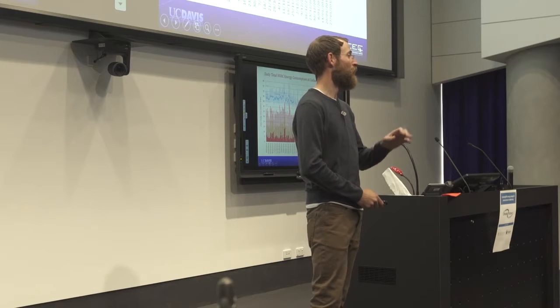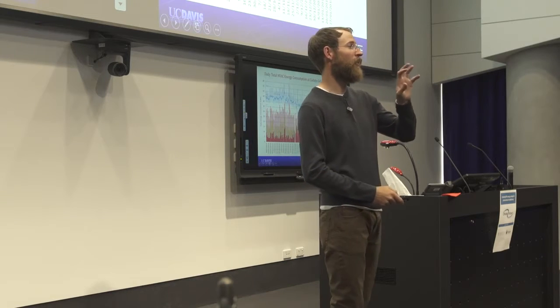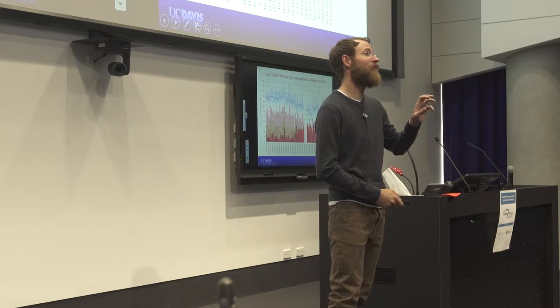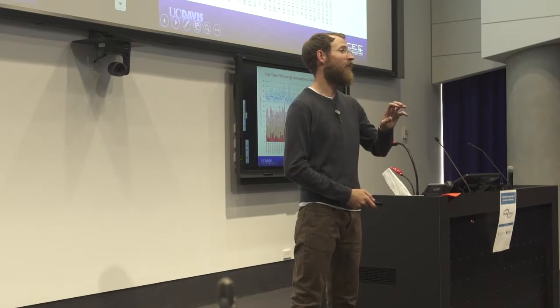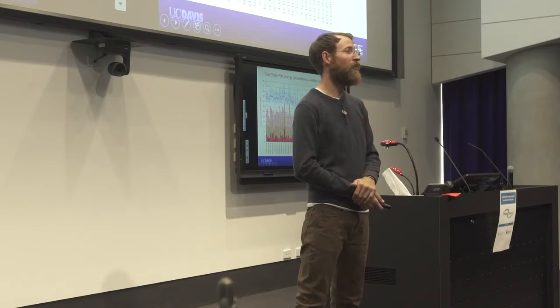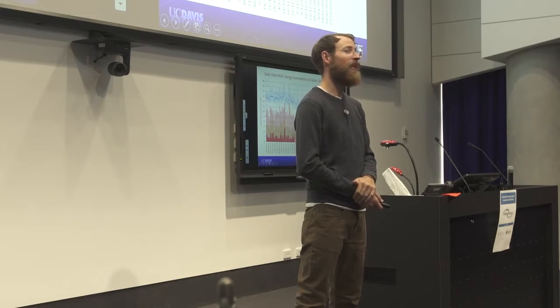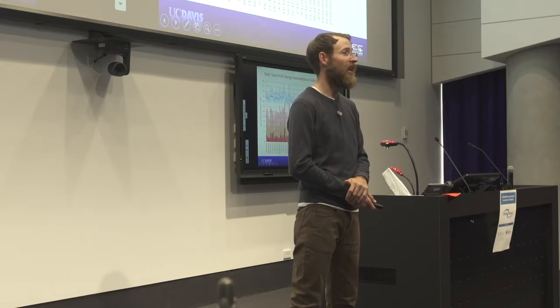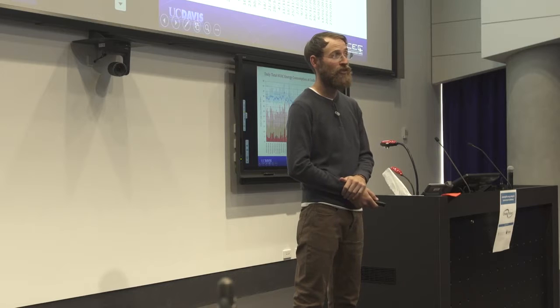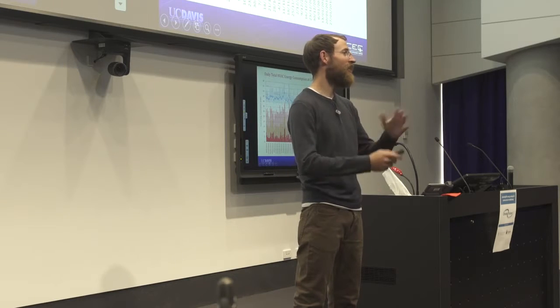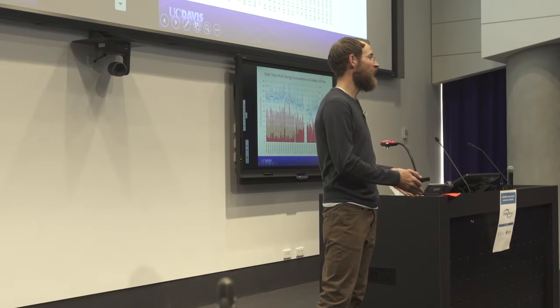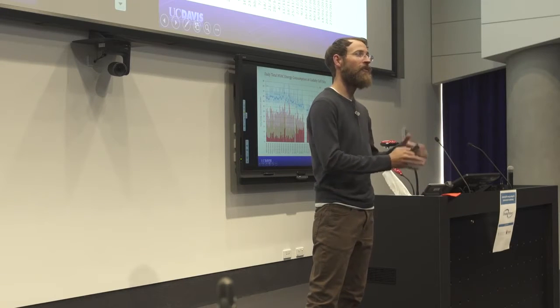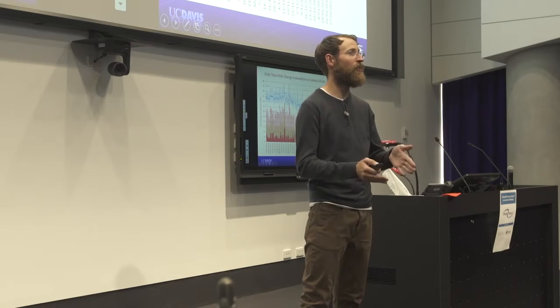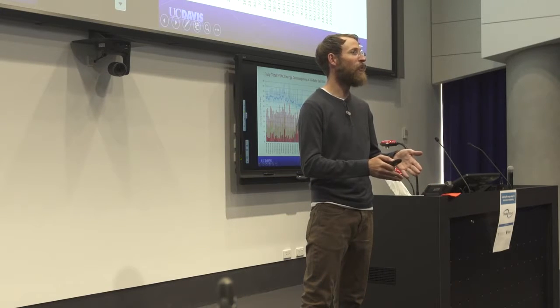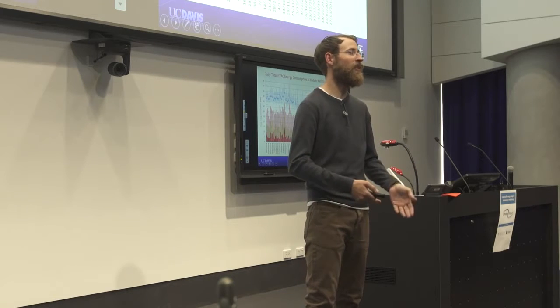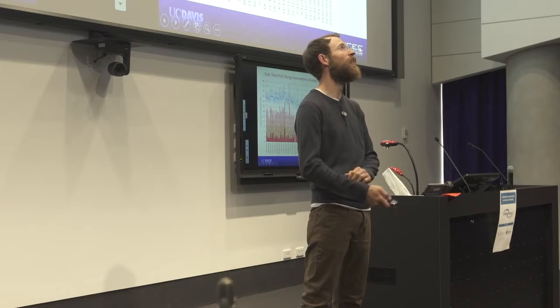We set up an experiment where we added the indirect evaporative cooler as a third system into that space, and we controlled everything in a way that gave priority to the indirect evaporative cooler so that it had the chance to operate first, and then if in any instances it wasn't capable of holding the temperature, the compressors could still come on. And then we set up the entire experiment in a way where in one day we would operate as the baseline with compressor-based systems only, and then the second day we would turn on the indirect evaporative cooler, and then the following day back to compressor systems only, and the following day back to indirect evaporative cooler.